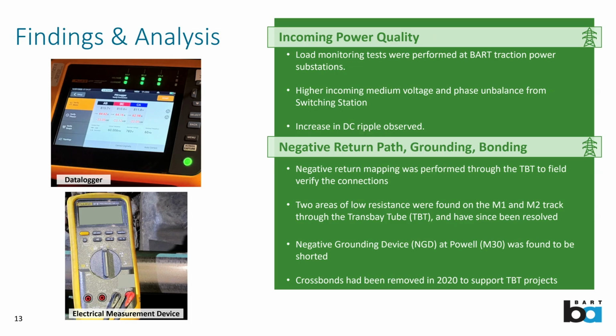And when we account for the turns ratio, we calculate that back, and we were able to determine that instead of 34.5 coming in, it's closer to 35.5 kV on the B and C phase and 36 kV on the A phase. So overall, though, this is really a change of less than 5%, which is considered to be a tolerable limit. What we are currently looking at is, what were the harmonics associated with that, and did they result in any unwanted frequencies on that DC side that perhaps the vehicles cannot tolerate.